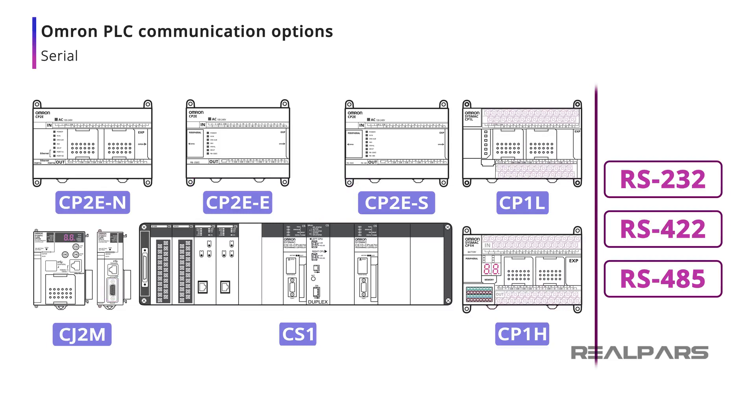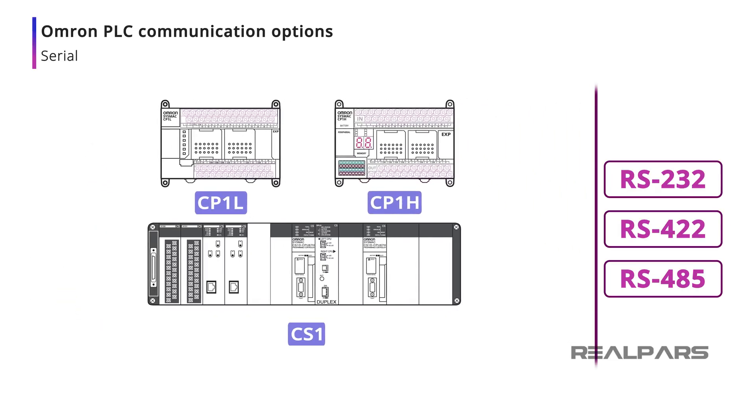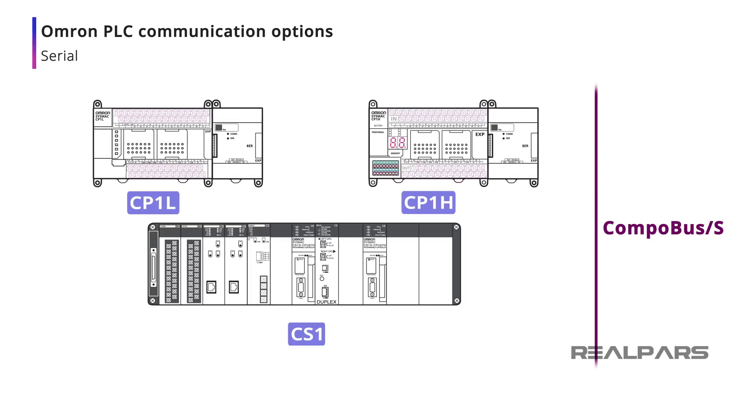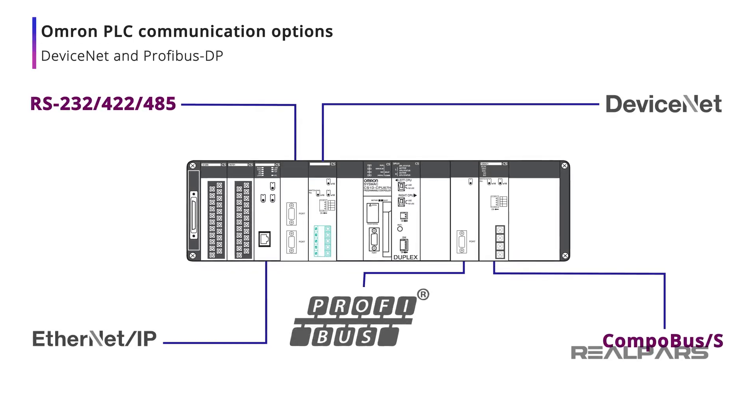In addition, the CP1E, CP1L, CP1H, and CS1 CPUs support Omron's proprietary CompoBus/S I/O subsystem, which allows for high-speed long-distance remote I/O connections. DeviceNet and Profibus DP are supported by the CS1 CPUs, so that additional device types such as weigh scales and motor drives can be connected to the PLC network.